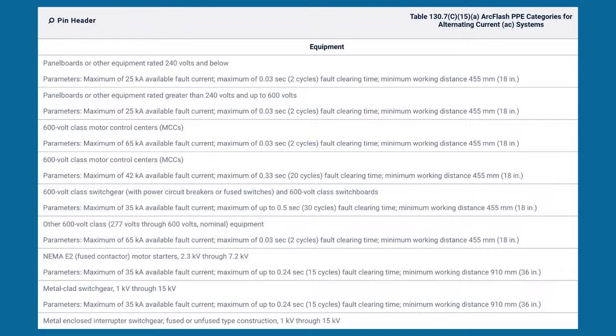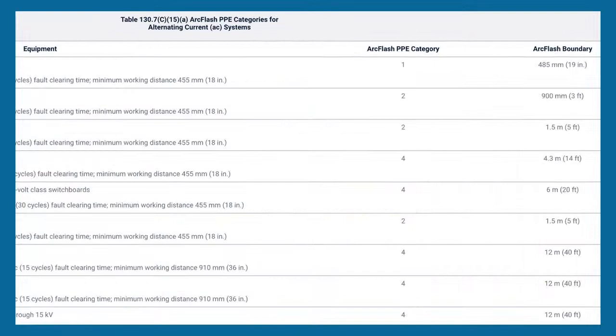Gotcha. Okay? Now, when I come over and look over here, I was looking at the second one, and you'll see I come across, it says the hazard risk category was a 2, and the arc flash boundary had to be at least 3 foot. Now, in this case, if I did my limited approach boundary, now I'm at 3.5 foot. The 3.5 foot exceeds the 3 foot, right? Yes, sir. Okay, so that's going to be your very minimum based on shock protection.